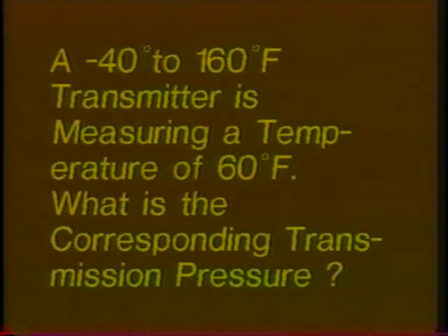Here are 2 sample problems for you to copy down and solve. Take 5 minutes to copy the problems and calculate the pressure equivalence. Problem number 1. A minus 40 to 160 degree transmitter is measuring a temperature of 60 degrees. What is the corresponding transmission pressure?